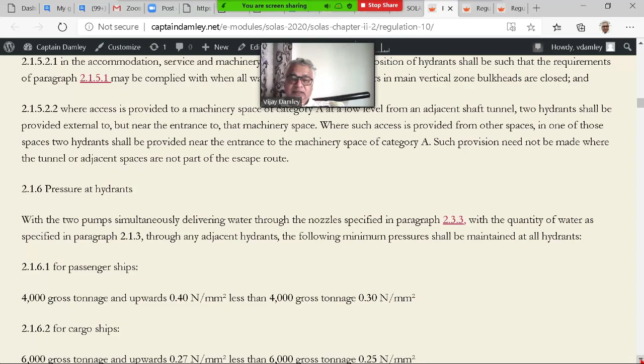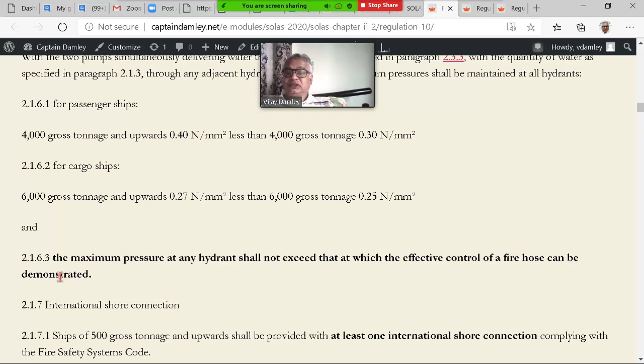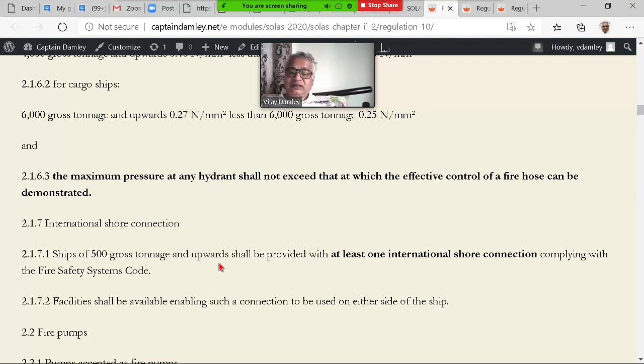Also another thing, the pressure at the hydrants: the pipeline which is made out of steel can withstand the pressure, but similarly the fire hose also must withstand the same pressure. It should not burst when I close the valve at the nozzle end. That is the whole thing. So you see every small point is covered up, so nothing should go wrong. Okay, this maximum pressure at any hydrant shall not exceed that at which effective control of the fire hose can be demonstrated. That is what I said earlier. Now we come to the international shore connection. Minimum one, generally you will find at least two.